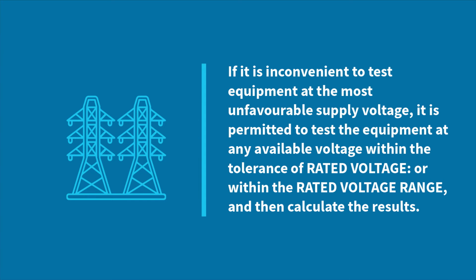If it is inconvenient to test equipment at the most unfavorable supply voltage, it is permitted to test the equipment at any available voltage within the tolerance of rated voltage or within the rated voltage range, and then calculate the results.